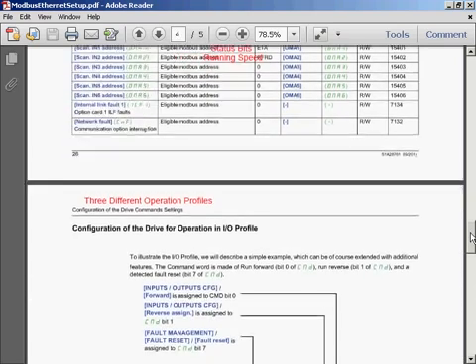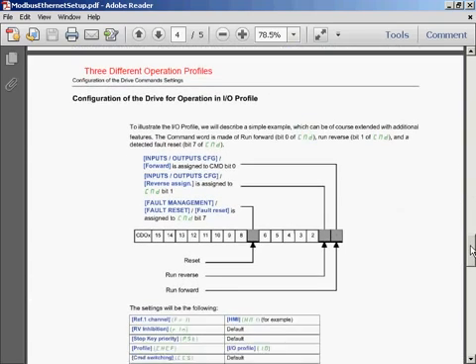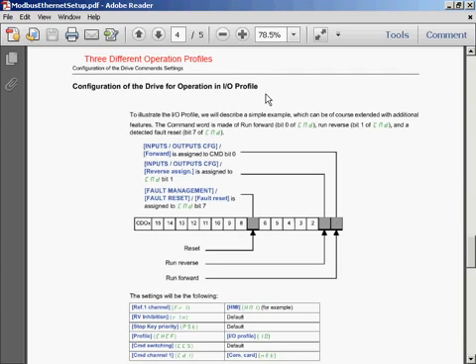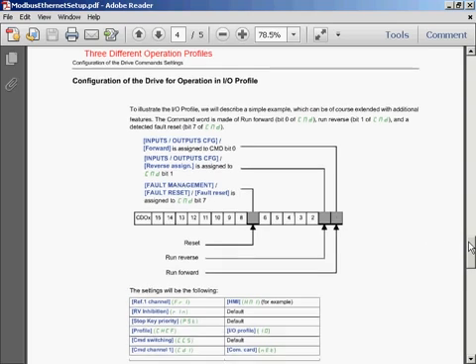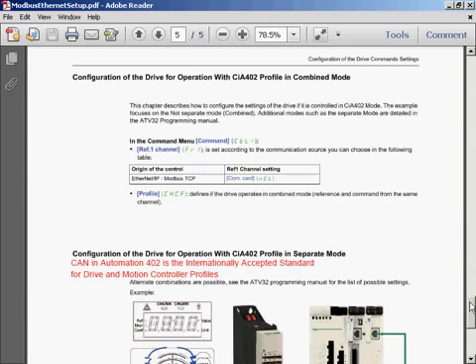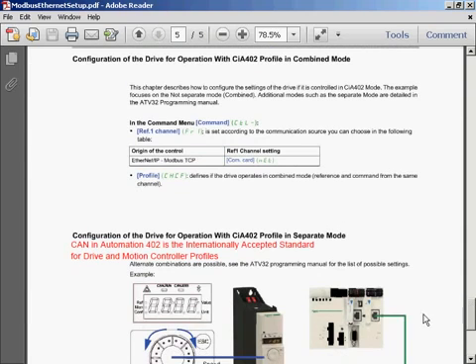As I scroll down further through the document, I've grabbed excerpts out of the document, but there are three different operation profiles that we can set up in the drive. The first is quite easy. It's just setting the drive up for I.O. profile. That way the communications that you use mimic the terminals that are on the drive itself. So the other method of controlling the drive is using the CiA 402 standard. This is internationally accepted for drive and motion controller profiles.